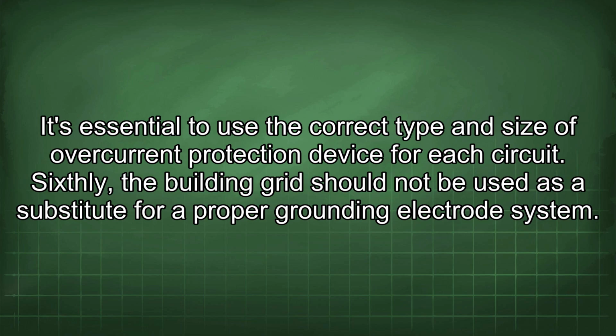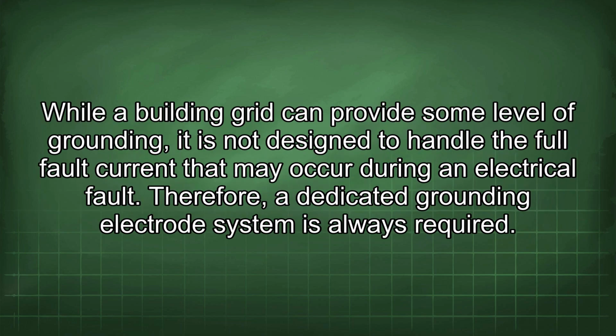Sixthly, the building grid should not be used as a substitute for a proper grounding electrode system. While a building grid can provide some level of grounding, it is not designed to handle the full fault current that may occur during an electrical fault. Therefore, a dedicated grounding electrode system is always required.